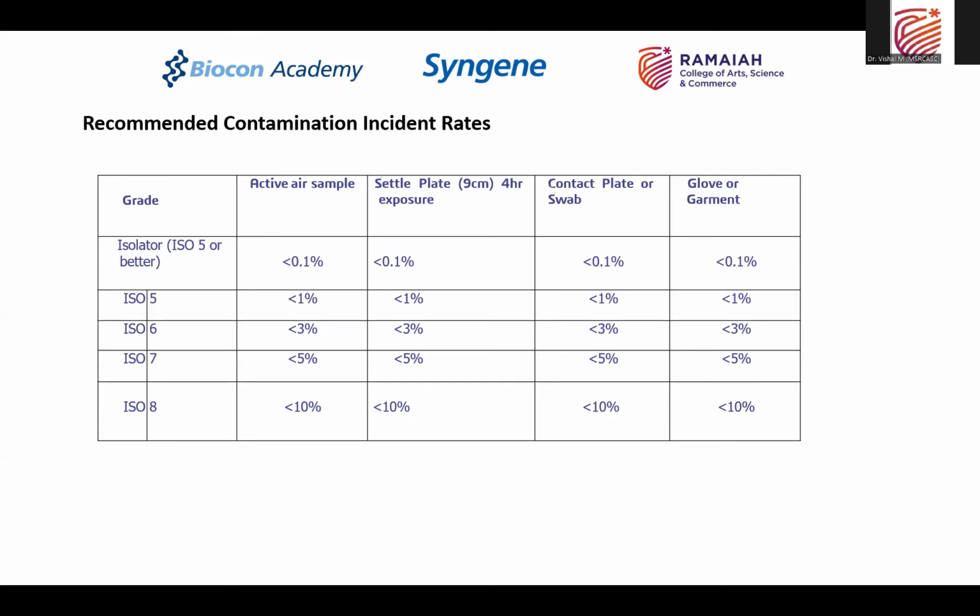So here you have another method. One thing is active air sampling. Another method is settle plate exposure. You expose a plate containing some media for so many hours, maybe 4 hours or maybe 1 hour. You can even expose it for 5 minutes.